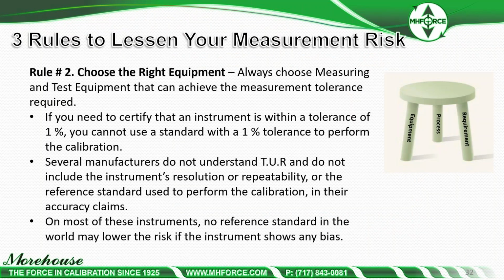So number 2, choose the right equipment. Always choose measuring and test equipment that can achieve the measurement tolerance required. If you need to certify that an instrument is within a tolerance of 1%, you cannot use a standard with a 1% tolerance to perform the calibration. That's a 1-to-1. It's going to be a lot less than 1-to-1 when you do everything.